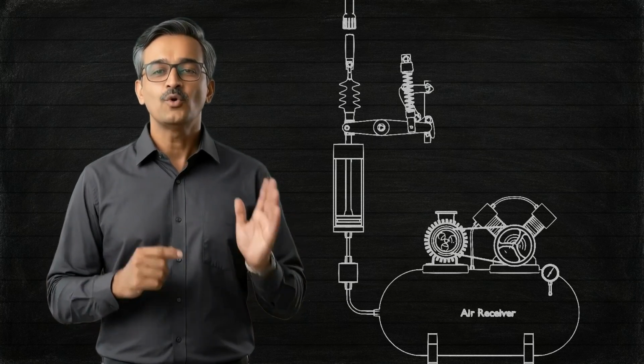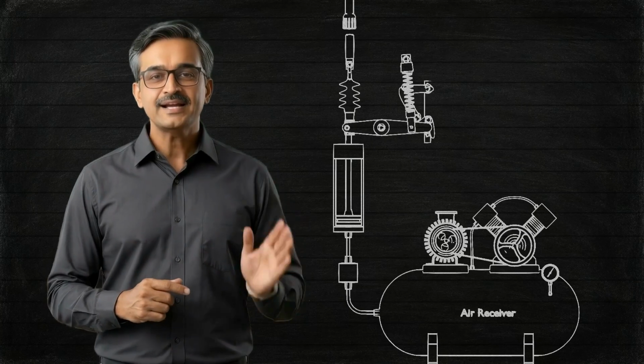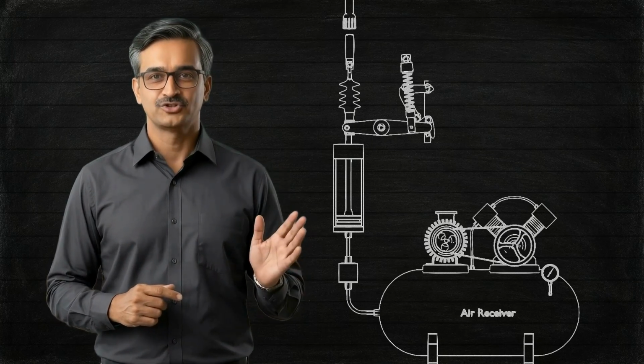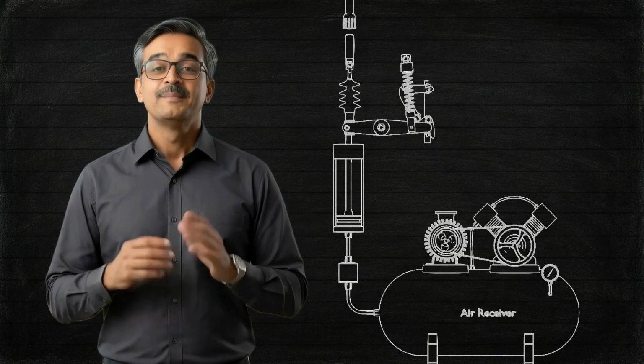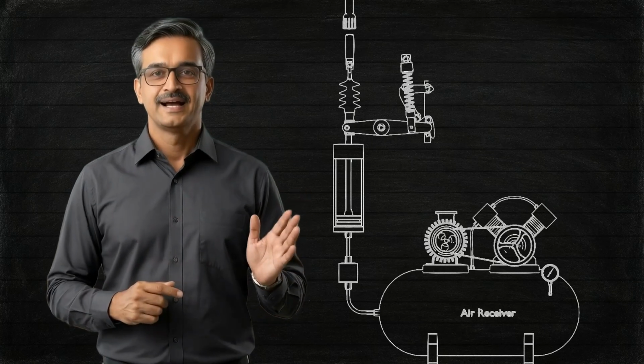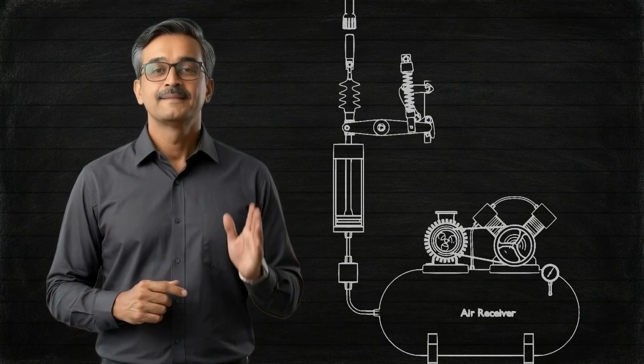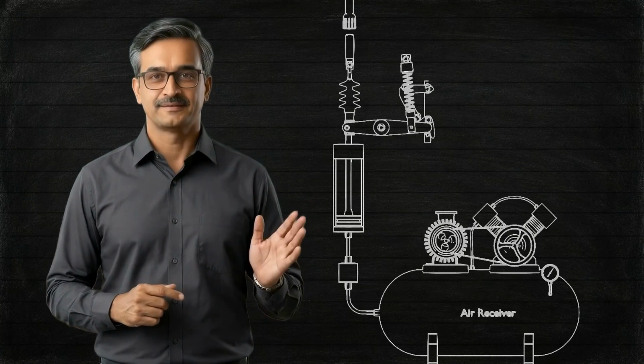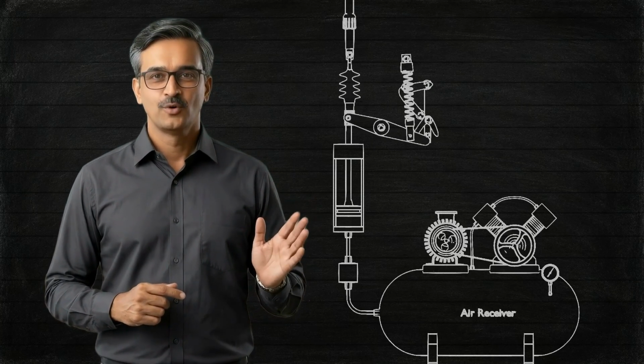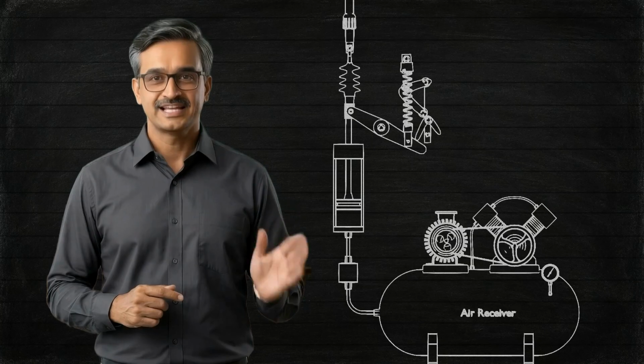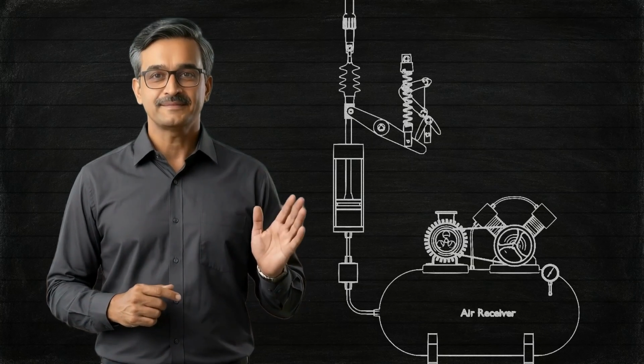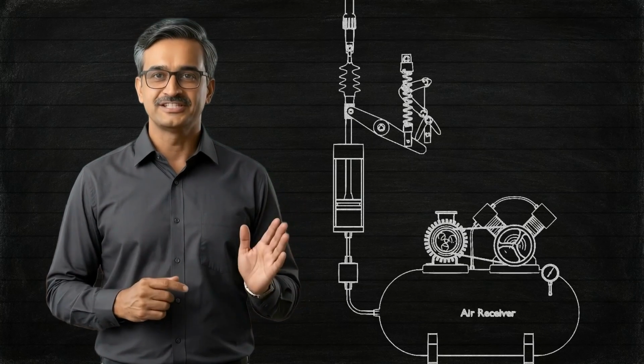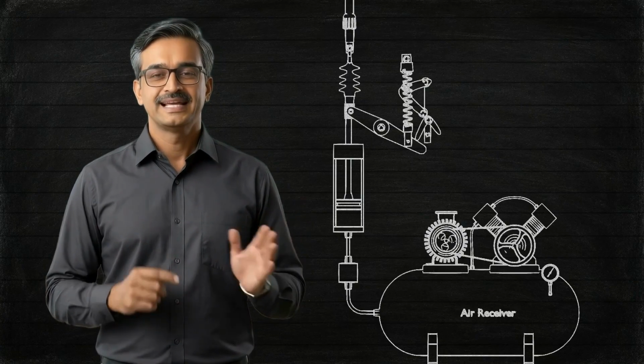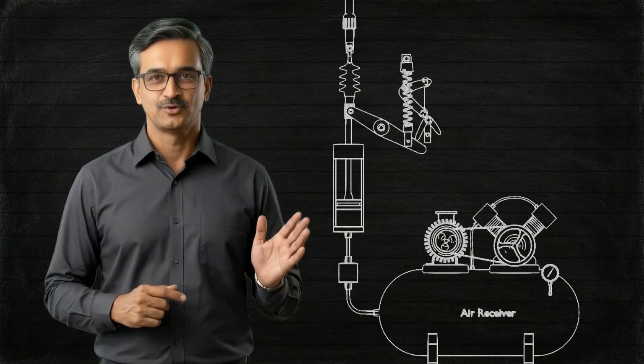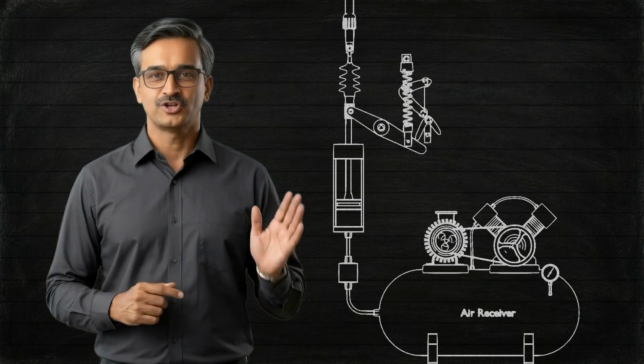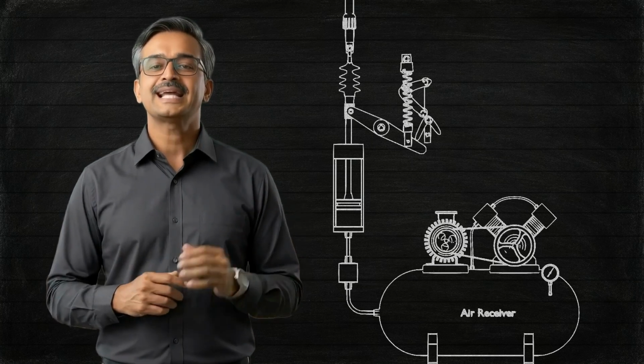As soon as the valve opens, high-pressure compressed air rushes from the air receiver into the pneumatic cylinder. The compressed air expands rapidly here and pushes the piston surface. The piston begins to move. The piston rod pulls the operating linkage. The linkage moves the moving contact. Finally, the circuit breaker closes. So remember, the electrical signal simply opens the pneumatic valve. The actual closing force comes from the compressed air.